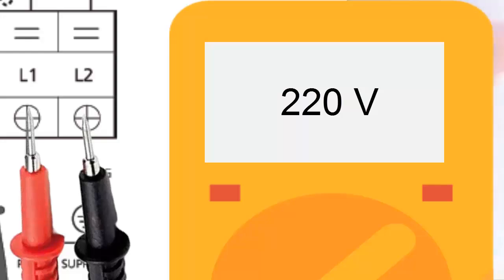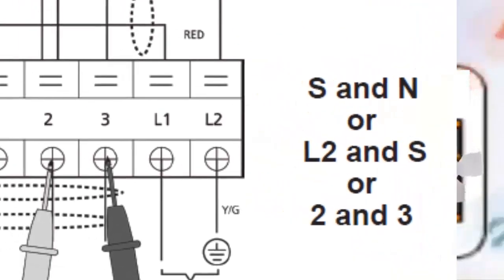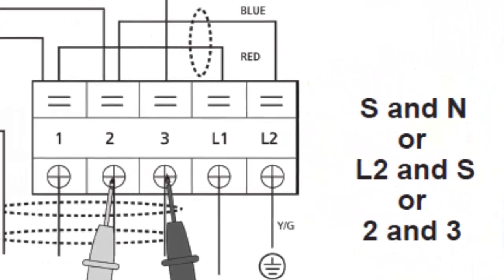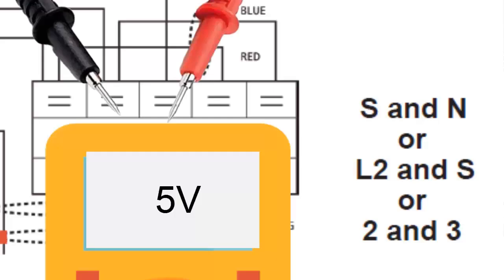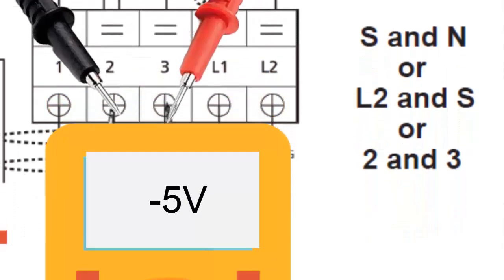5. Measure the signal voltage by following these steps. A. On the outdoor unit, use a multimeter in the DC voltage range. B. Generally measure the voltage between port 2 and port 3 of the outdoor unit. C. Depending on the model, the signal wire may also be identified with the letter S or the number 3. D. To obtain the signal voltage measurement, measure it relative to the neutral wire or L2.